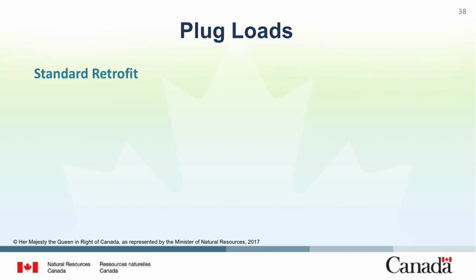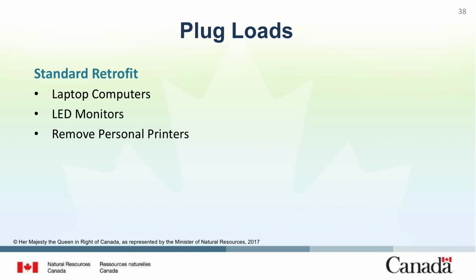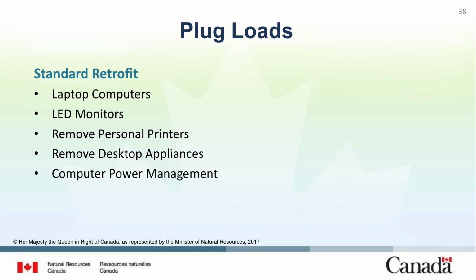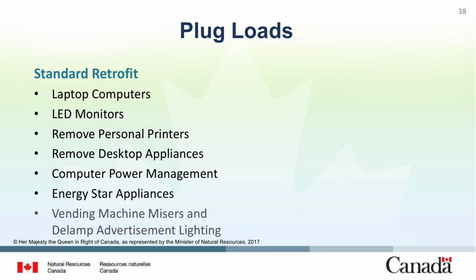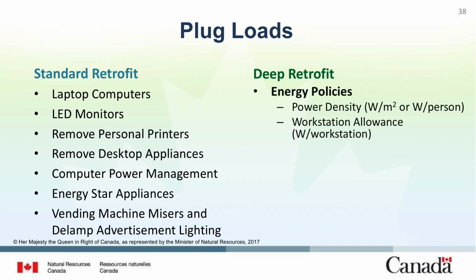On this slide, standard retrofit items are listed on the left. There are things that are typically done, such as changing desktop computers to laptops, computer power management, and LED monitors. When it comes to a deep retrofit, what we're doing is similar to what we've just presented through lighting. We're talking about a different approach to reducing loads by setting either a power density requirement or workstation allowance. A workstation allowance would only allow so many watts per person, which is drastically different than the current approach, which allows unregulated watts per square foot or watts per person.